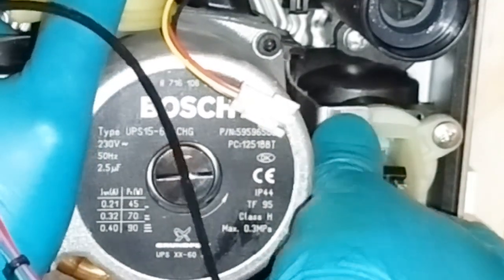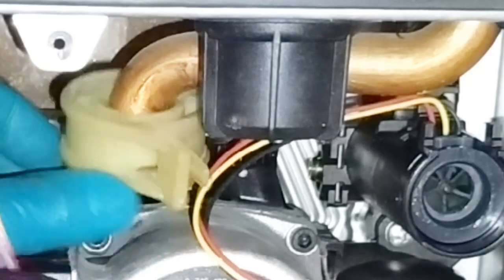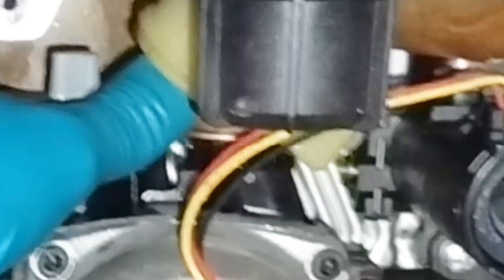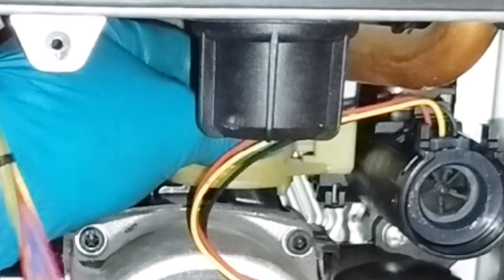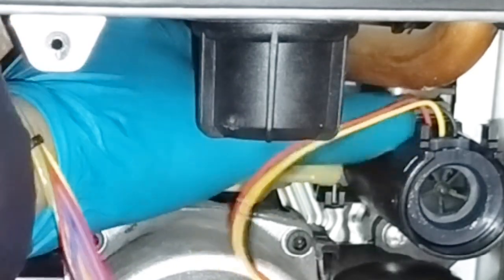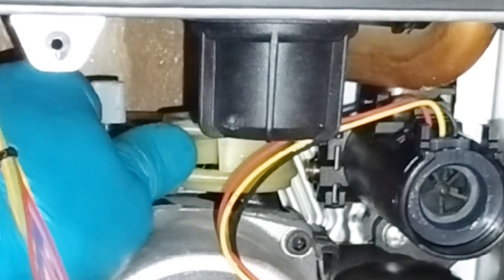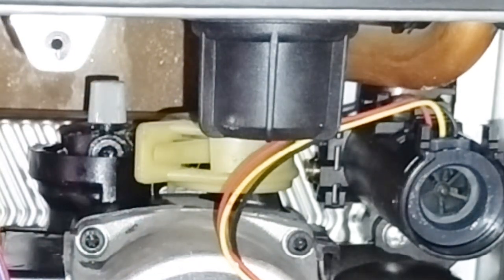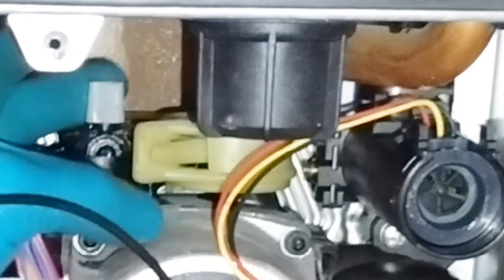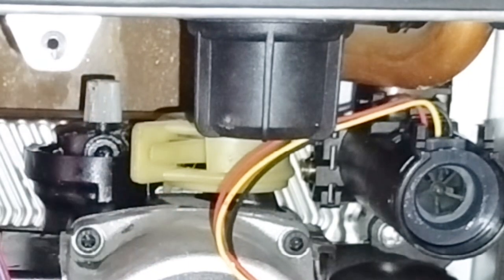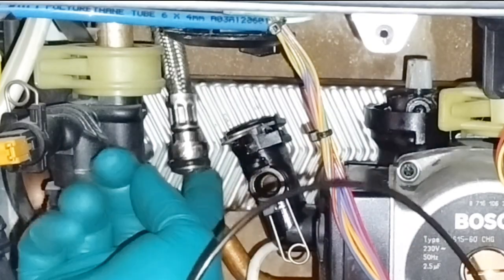We had replaced the seal on top of the pump earlier, which I didn't show, and this little lip has to sit inside where I've just shown. I repeated the clip a few times just to show you how it's done. You put the locking clip back into position, and it rotates clockwise. At the same time, I've loosened up the AAV, so when we fill the system up, it starts to release any air and it doesn't get trapped.